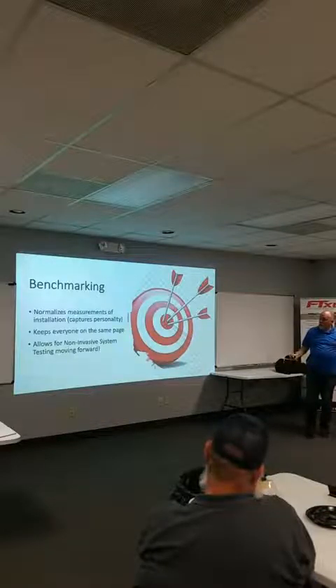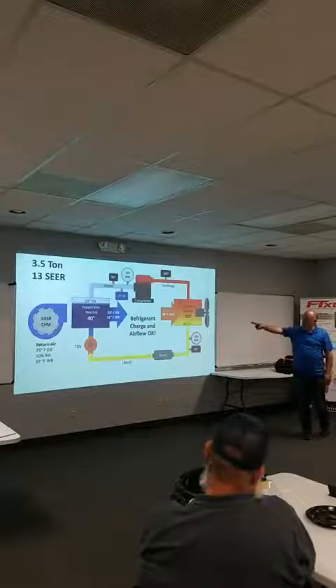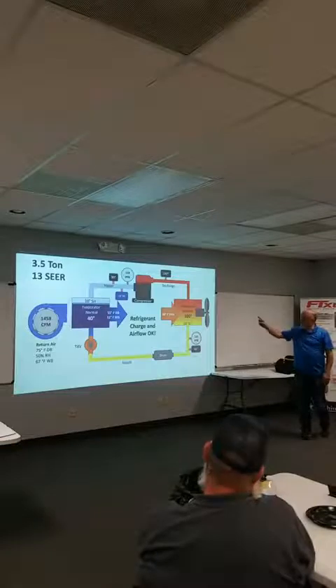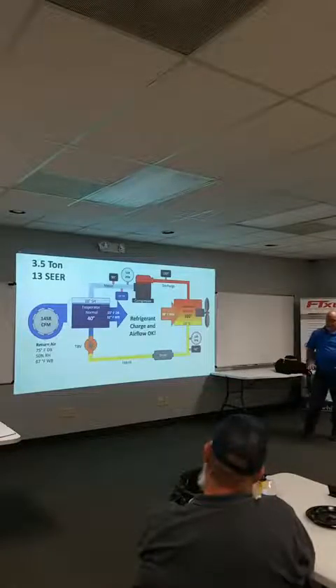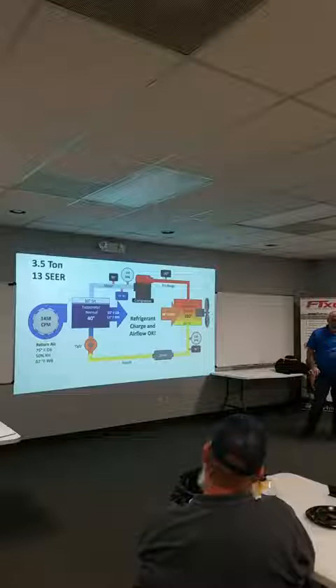So benchmarking, once we get this system right, once we have the airflow set, we have the superheat correct, we have the condenser correct, we're gonna benchmark the system. It's gonna capture the personality. Now here's a key thing with that.